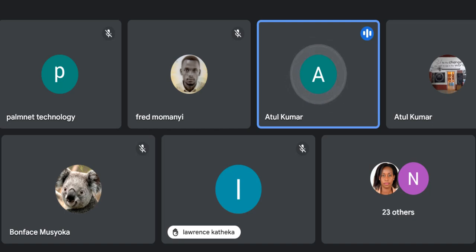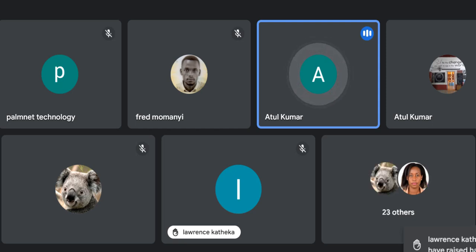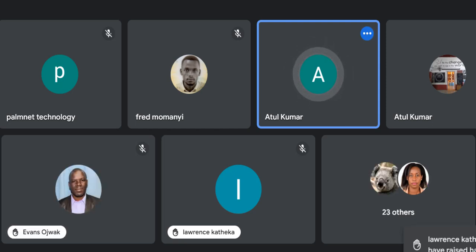Obviously, if you are having different energies, you'll have to put in different flattening filters and different electron scatterers. So you'll have to have a carousel. That will increase your size, which you cannot afford in CyberKnife, tomotherapy or Halcyon. So these machines are explicitly designed for compactness, and that is why you have only single energies. But those machines which are designed for higher energies, like TrueBeam, Versa HD, Edge, and several other machines, have multiple energies. Thank you so much.